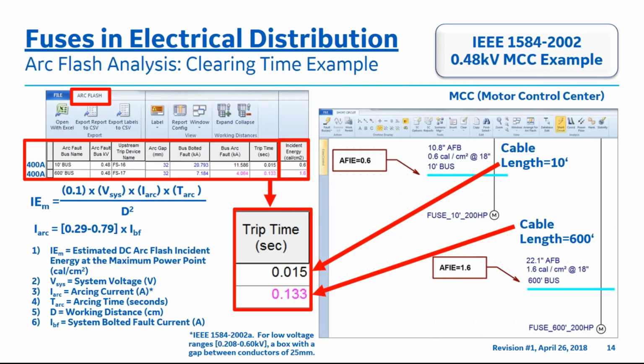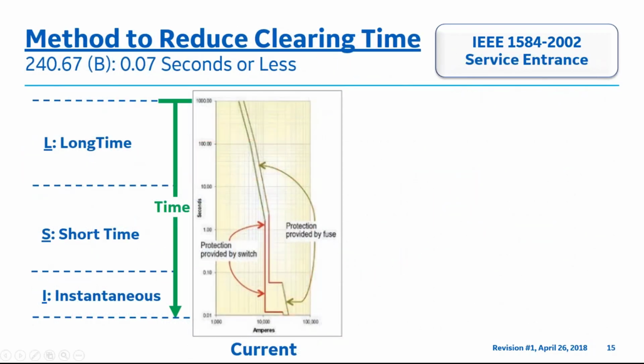Now that we have completed an engineering low voltage arc flash analysis for fuses with different arcing current clearing time examples, being extremely important for fuses, let's begin to apply the 240.67 code for paragraph B. Reviewing the basics of a time current curve, LSI, which refers to long time region, short time region, and the instantaneous region, which are drawn on the left.